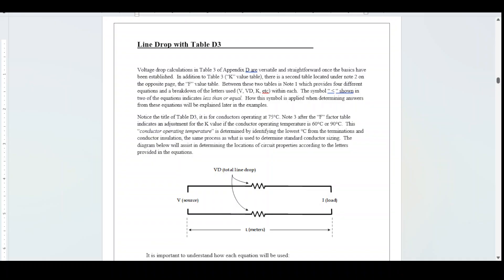Notice the title of table D3 — it is for conductors operating at 75 degrees centigrade. Note 3 after the F-factor table indicates an adjustment for the K-value if the conductor operating temperature is 60 or 90 degrees centigrade. This conductor operating temperature is determined by identifying the lowest degree centigrade from the terminations and conductor insulation, the same process used to determine standard conductor sizing.